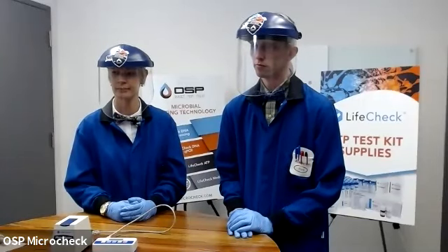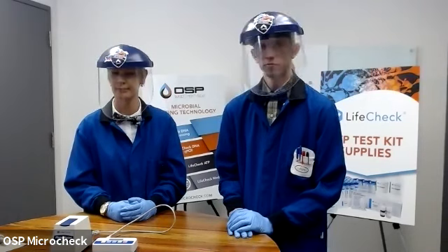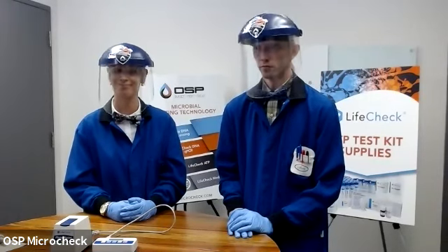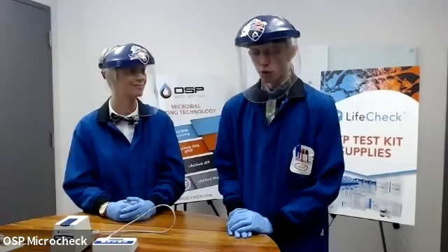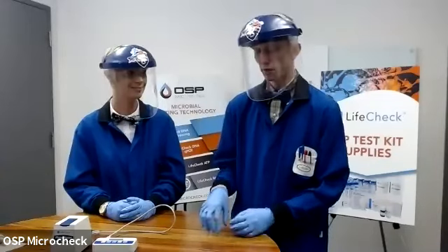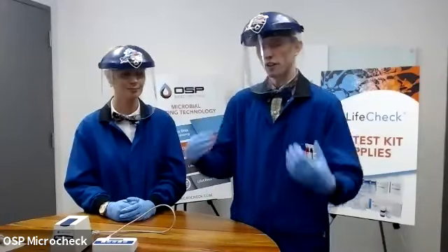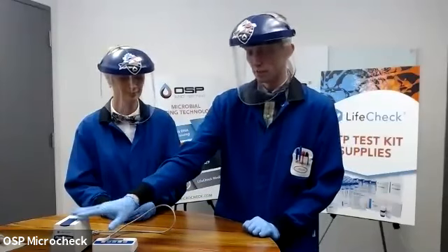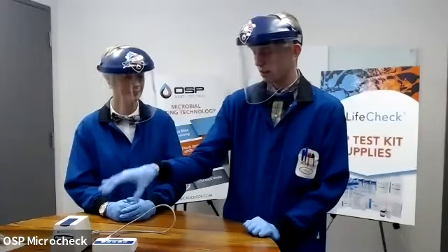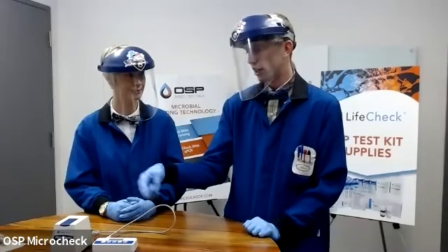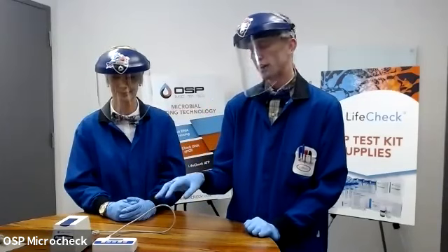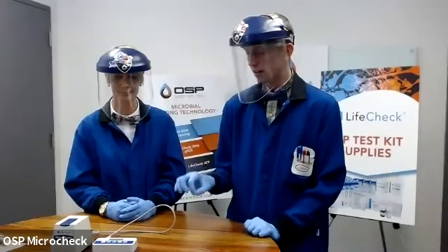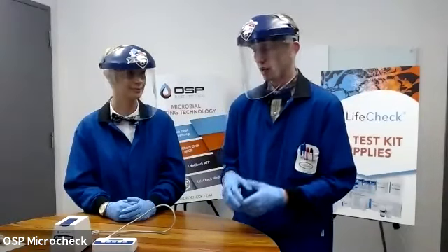Okay, and last question for just this section, and then don't worry, we'll get back to the rest of these, is how often do you run background checks on your enzyme? Every hour during the day, or what's the general timeline, if you will? Yeah, so you don't have to run that standard for every single sample within a batch of samples. So let's say I collect 10 samples and I want to measure them all in this instrument. I'm going to start off with one background and one standard. Running the background on each can be important to test the tube that you're using for each individual sample. But the standard itself to test for that enzyme health, that's really a batch effect thing, right?